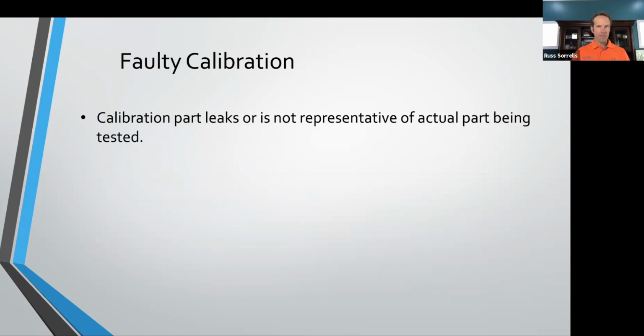Then it relaxes, lets everything come back to ideally a normal temperature and state, and then we run a second test. In that test, we introduce the leak standard. The leak standard is mounted normally internal on the manifold of the instrument, and it opens up and establishes our upper test limit. So the pressure loss associated with the part and the leak standard go together to establish our upper control limit. When we calibrate, let's say our leak standard is not impactful and we're too close, so we don't have a good ratio between the two, that causes all kinds of problems.